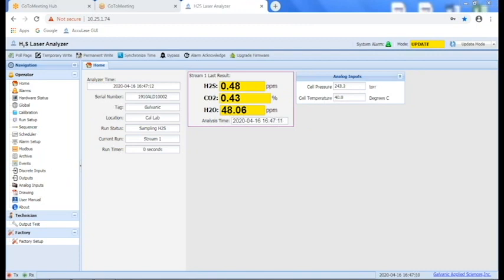Sometimes you'll see some of the numbers jump around a little bit, so I'll walk you through the sequence of what happens. When it's sampling H2S, H2S and CO2 are analyzed by the same laser. In this analyzer, we have two lasers inside, coupled to the cell through a fiber optic splitter. When it's measuring H2S, which it is right now, we set the drive current of the laser so it puts out a wavelength that corresponds to an absorbance feature of H2S.